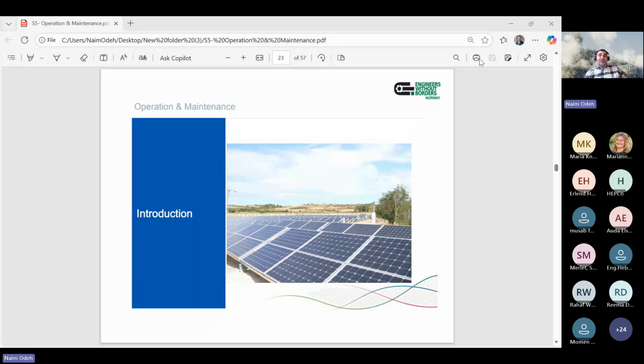This depends on the country and on the soil, since the system will be grounded at the end. But on average for a lightning protection system, they usually ask for 10 ohms, and for an earthing system, up to 1 ohm. This shouldn't be applied by default everywhere, but these are the common recommended values. When you build an earthing system, it's important to aim for up to 1 ohm, and for lightning protection, up to 10 ohms.